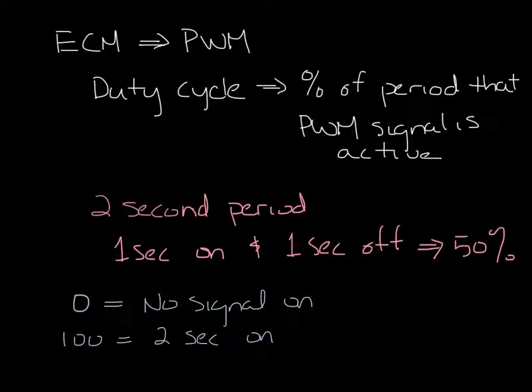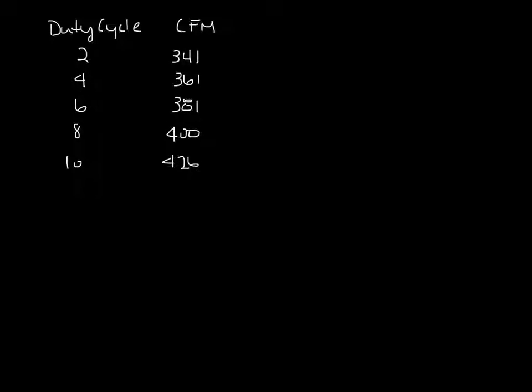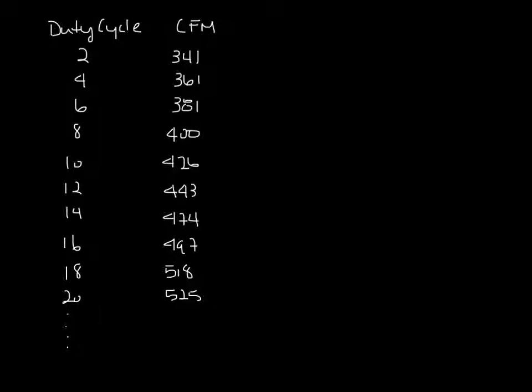In the ECM podcast, I mentioned that the motor has a microprocessor that, when programmed, allows it to control the airflow regardless of changes in pressure. It's a pressure-independent motor. Because of this, we can tell you the CFM output of our fan box at any given duty cycle. In fact, we put a chart on the side of the box that looks something like this. So at 2%, it's 341 CFM, at 4%, 361, and so on. And then we'll just keep going here all the way to 100%. The duty cycle of 20 would correspond to a voltage signal in the PWM of 2.0 volts.